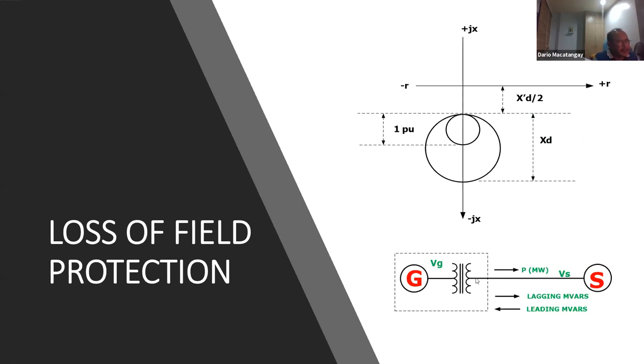The Mho characteristic is like an impedance characteristic. You know that impedance is voltage divided by current, and the characteristic is circular, okay? Typically, this is your positive inductive reactance here, and this is negative reactance here. When the system is normal, you would operate somewhere over here. Now, when there's a loss of field, this point will suddenly go inside here, right? So there are two sensitivity settings here, the zone one and the zone two.